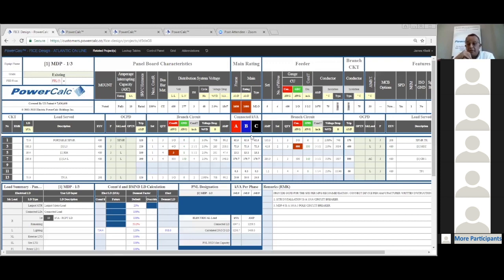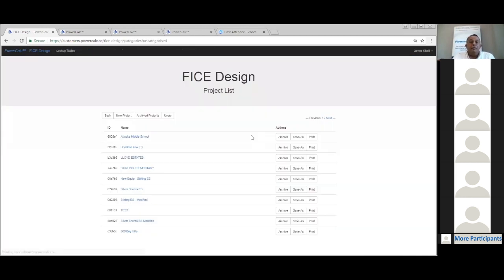That's very expensive. So that added expense to the project, or unnecessary expense. So they set up the transformers at 112, and then they started loading them with the load. And we found out that the maximum was like 30 and 45.